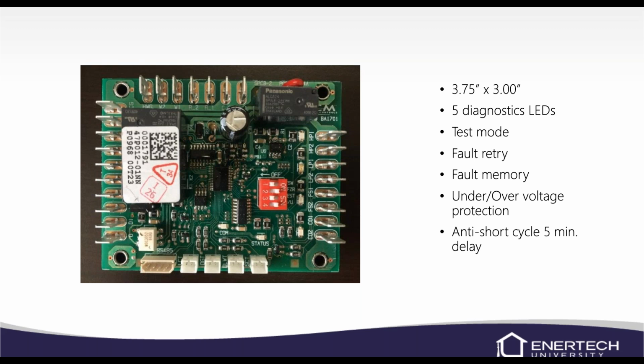There's a troubleshooting box that'll say, if you've got an orange light that's flashing and a yellow light that's solid, that means, let's just say, condensate overflow. It'll kind of tell you what that is. So there is a test mode. If you put it in test mode, it'll speed up your time delays. There's fault retry. So if it faults out, it'll shut down, wait 5 minutes, and restart and try to get the unit to run again.